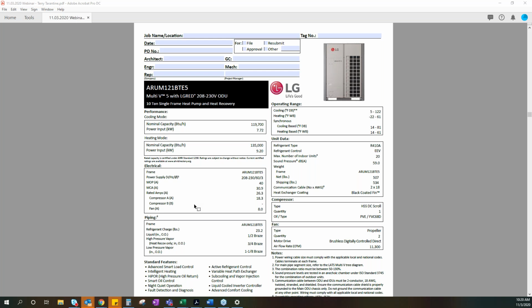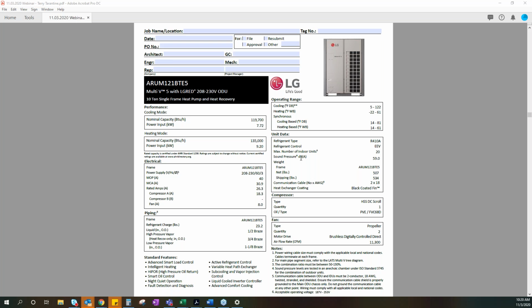Going down into the piping, you notice that the refrigerant pipes are 1/2 inch and 1.125" copper connections. Very, very small piping compared to the capacities. If you look to the right, under the unit data, the fourth section down is sound pressure, the decibels. It's only 59 dBA. 59 dBA, to put that into perspective, is about the same as a 2-ton residential system. And may I say, a very quiet 2-ton residential system. So again, these units are incredibly quiet.